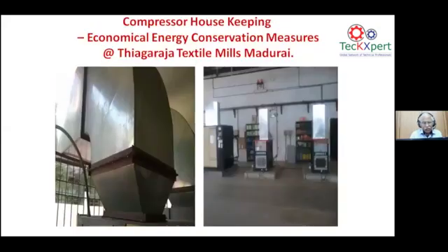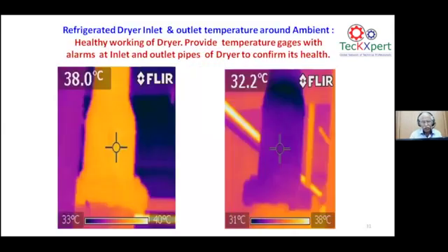Having done energy audits, we have suggested to many industries to expand the duct, or if that is not possible, to just put a 2 meter duct on the compressors. Automatically the hot air just goes to the top, it does not come back and is not sucked back into the suction. So economical energy conservation measures are also very much there, and this has been implemented in Thiagaraja Textile Mills at Madurai.